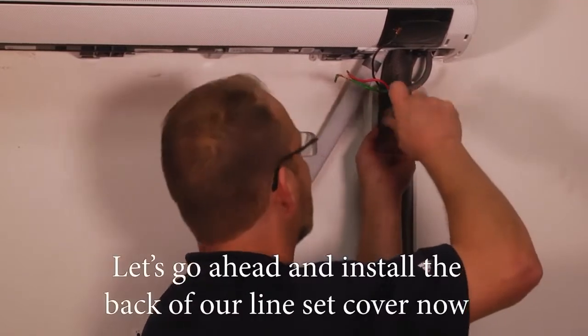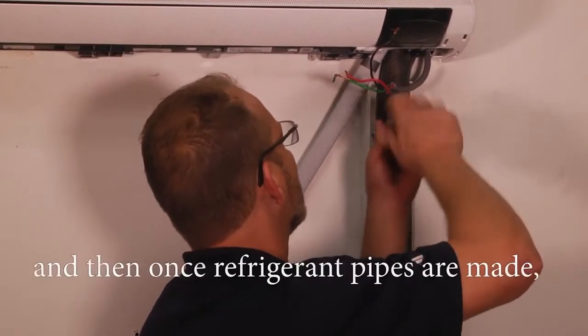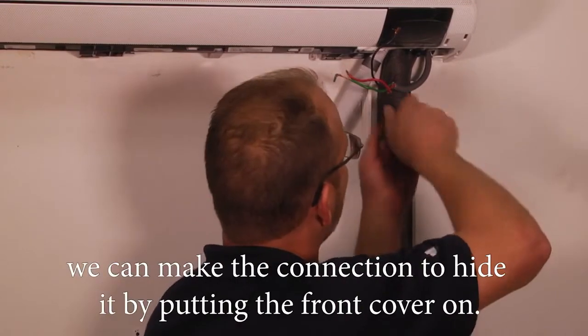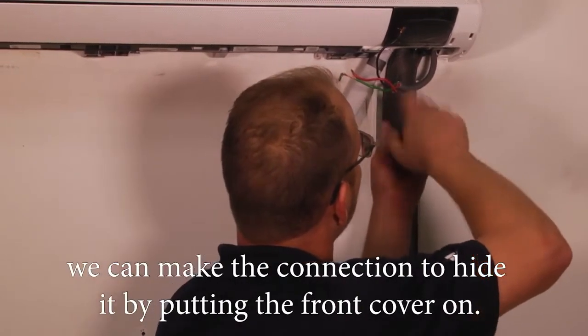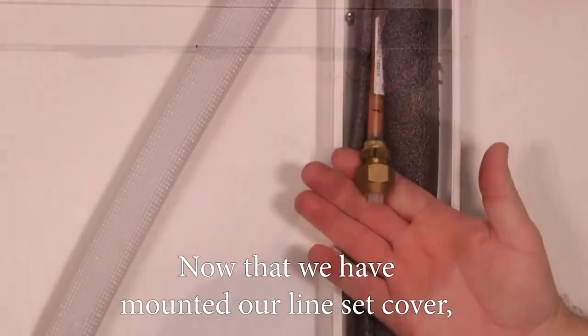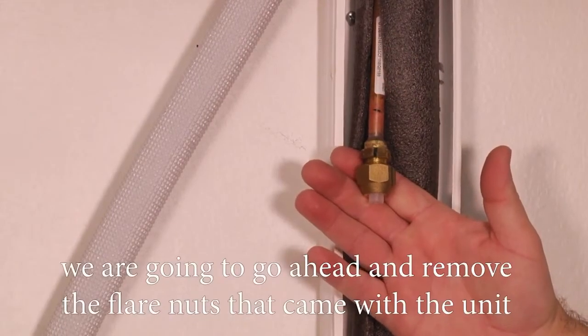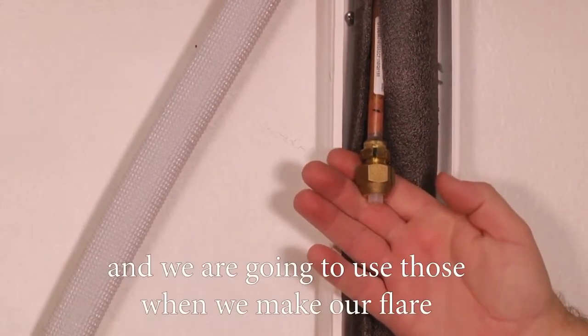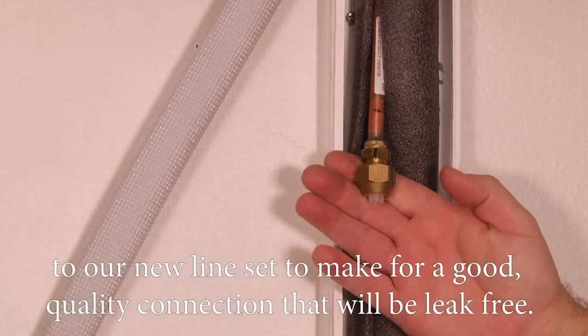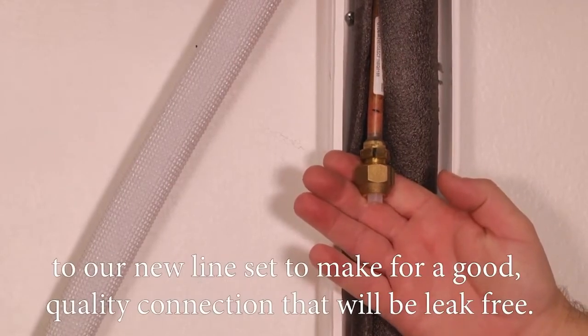Let's go ahead and install the back of our line set cover now, and then once the refrigerant pipes are made, we can make the connection to hide it by putting the front cover on. Now that we've mounted our line set cover, we're going to go ahead and remove the flare nuts that came with the unit, and we're going to use those when we make our flare to our new line set to make for a good quality connection that'll be leak-free.